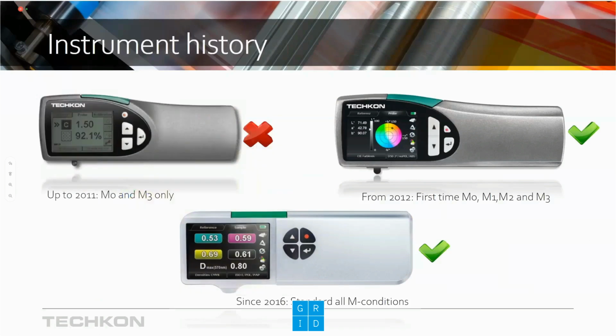If you have a look at the history of instruments, then it's quite easy to recognize if an instrument is able to measure M0 and M1. It isn't valid for our instruments only, but for other instruments on the market as well. As soon as your instrument has a color display, then you can mostly be sure that it can measure M1, because older instruments mostly had a grayscale display. So they could measure M0 and M3 only.